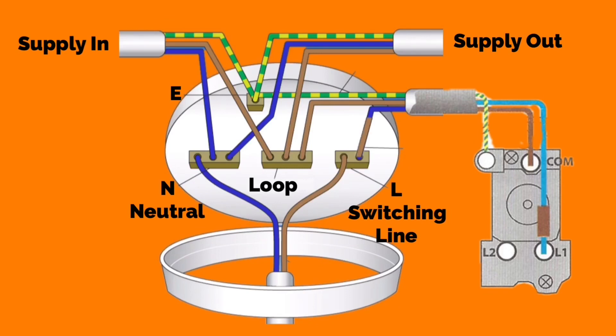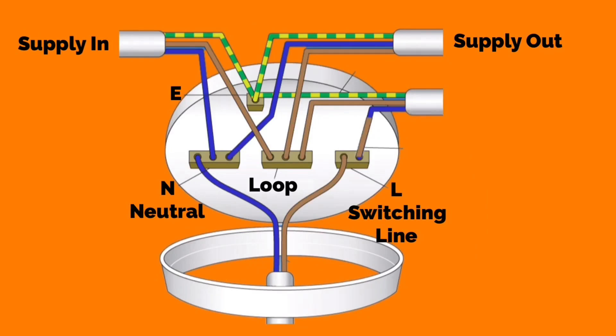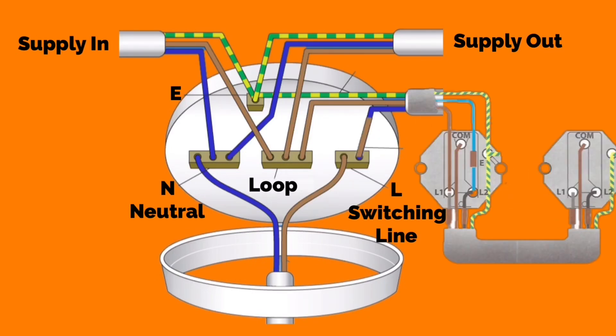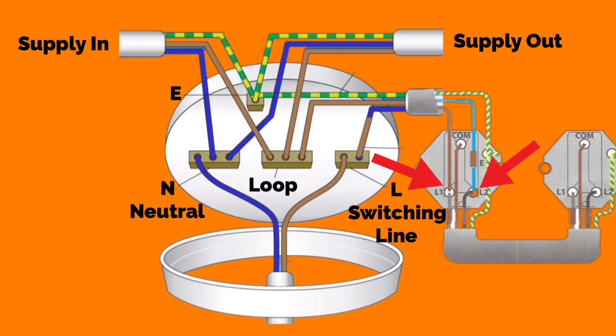This switch drop can be easily altered to two-way or two-way and intermediate switching. The cable shown for the one-way switch drop would be identical going down for a two-way configuration. With two-way switching, the drop to the first switch is still in twin and CPC. However, the terminations coming down will now go into L1 and L2, leaving the common terminal without a connection, and we introduce a three-core and CPC cable.